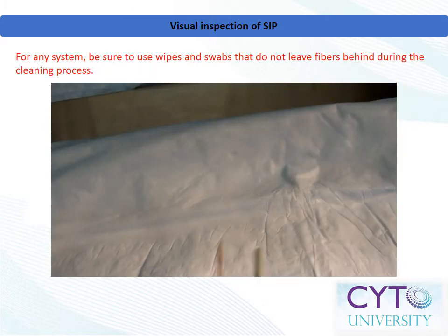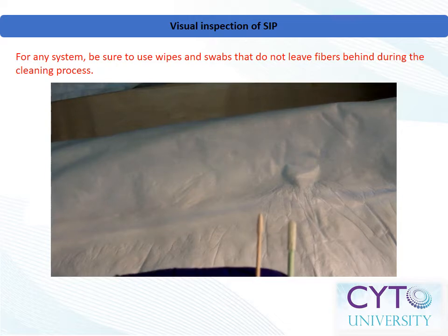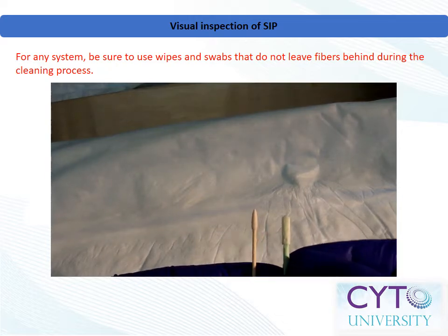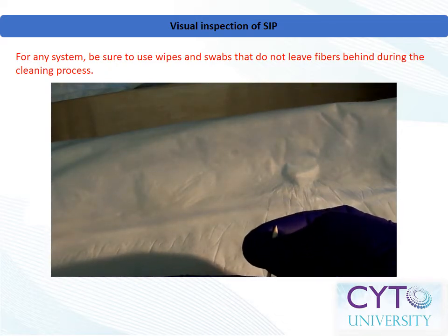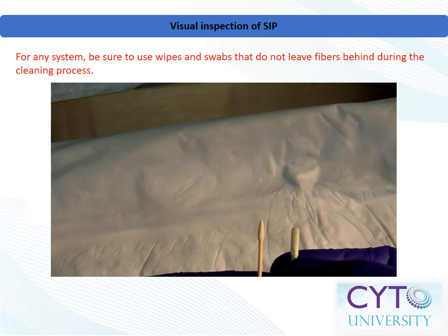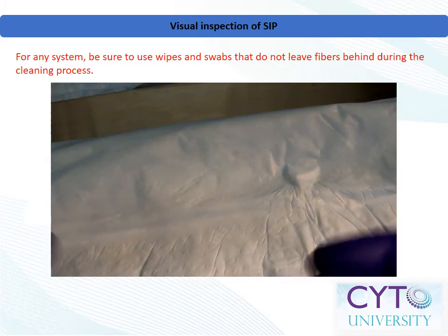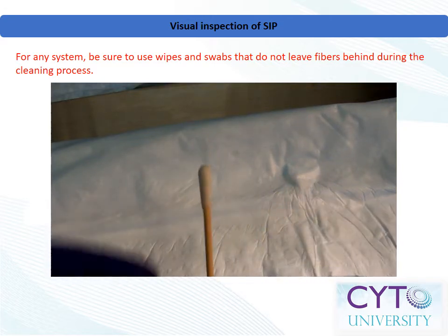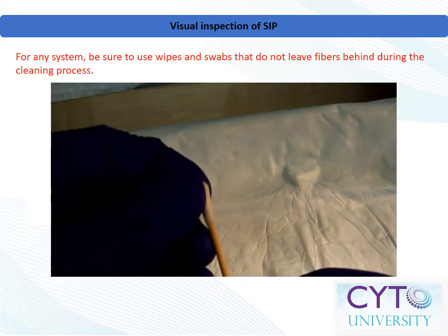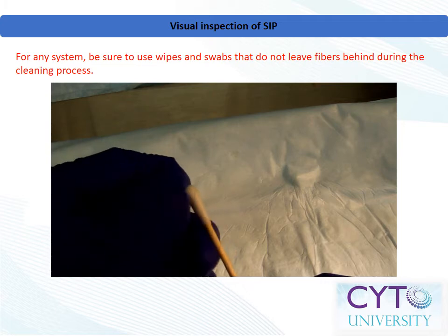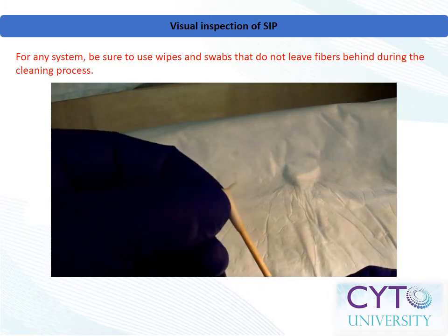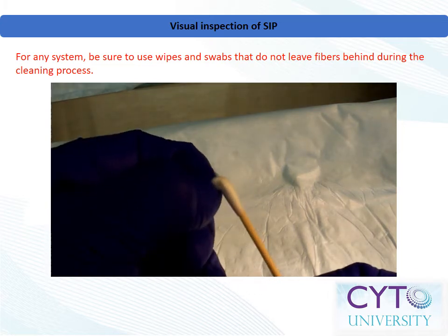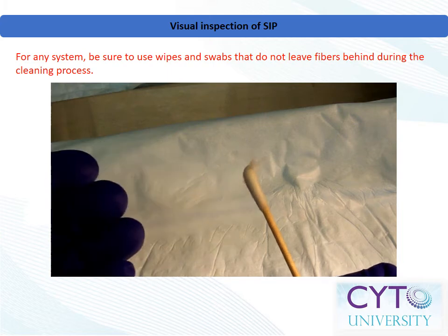For any system, be sure to use lint-free wipes and swabs that do not leave fibers behind during the cleaning process. Note that some swabs, such as the cotton-tipped applicator or third example shown here, can easily fray with light abrasion. When in doubt, perform a rip test to ensure the durability of your cleaning materials.